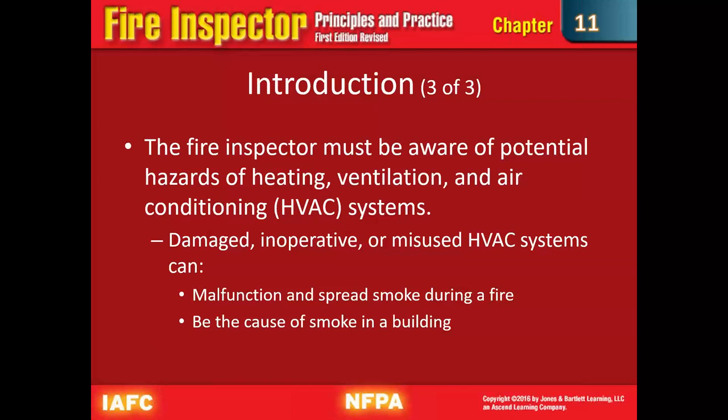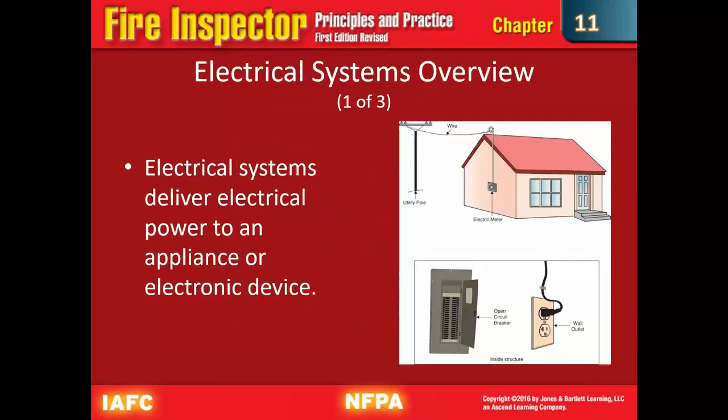We also need to be aware of the hazards of HVAC systems. They can be damaged, inoperative, or misused. They can malfunction, spread smoke during a fire, and be the cause of smoke in a building. How many times do we get called out to smoke in a building and it's an HVAC blower motor or fan motor that's smoking out? I've also seen a couple of times where that was the cause of fires.